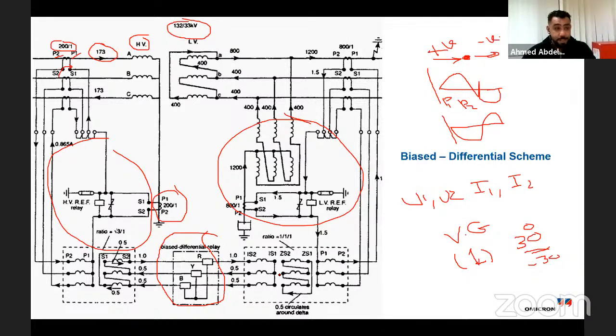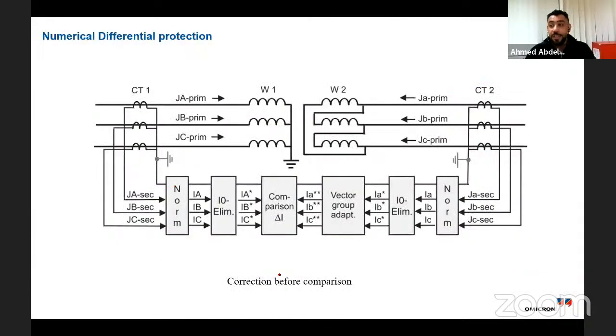Now, nowadays, I don't need to do any kind of calculation. I need just to have a protection relay, which does the comparison of delta I. This is our numerical relay, and everything will be done inside the protection relay. I don't need any CTs. I don't need any polarizing calculation. I don't need to have a resistance. I don't need to find the interposing CT.